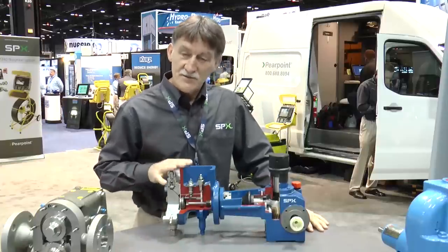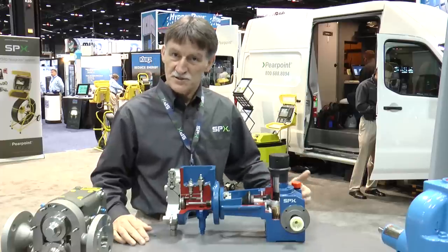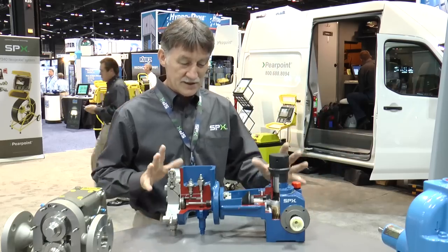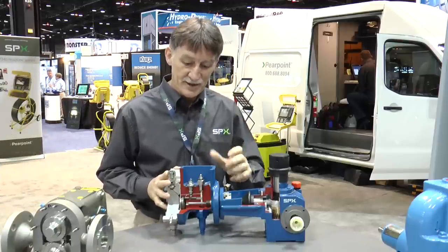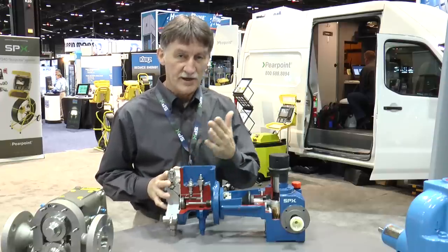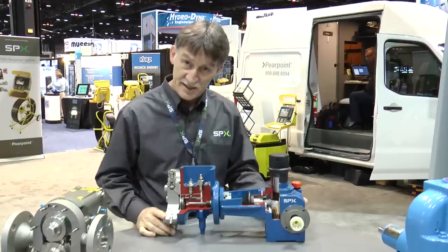The next application is chemical dosing into the waste stream after all the filtration has been accomplished. The stream must be pH neutralized and any other chemical contaminants removed before it can be returned. In this case you use a chemical metering pump, which is typically very accurate, and it has to be sealed because you're going to be pumping things like sulfuric acid, caustic, sodium hypochloride, and ferric chloride. You don't want fugitive emissions, you don't want leaks, you don't want environmental contamination.